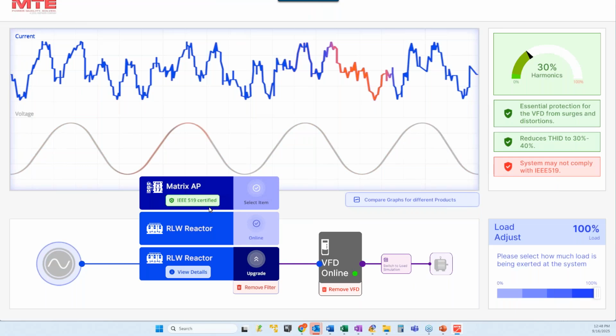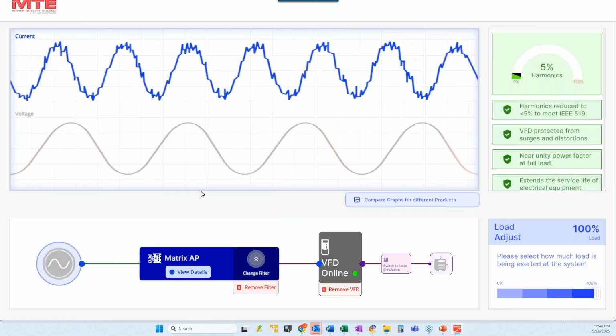And then they've got what they call the matrix AP filter, which is IEEE certified. And that, for the load, is cleaning up the harmonics enough so I'm less than 5% harmonics. Actually, the new standard is 8%. So the 5% is a little misleading. It used to be 3 and 5, now it's 5 and 8, which I kind of showed you in the presentation on harmonics. So that's your solutions on that.